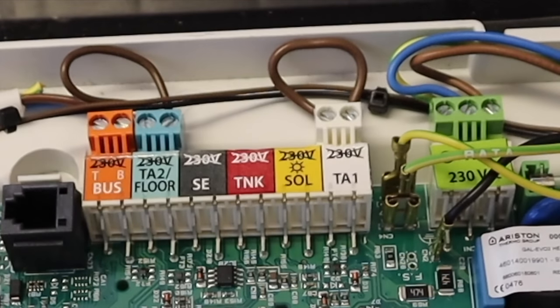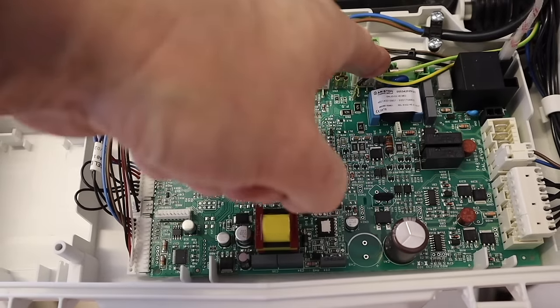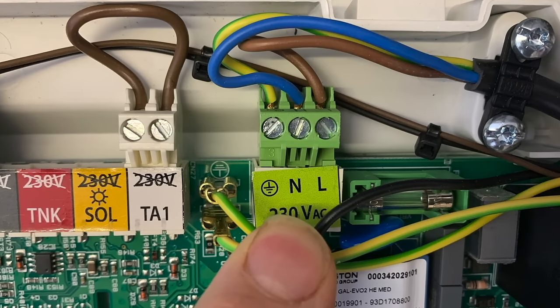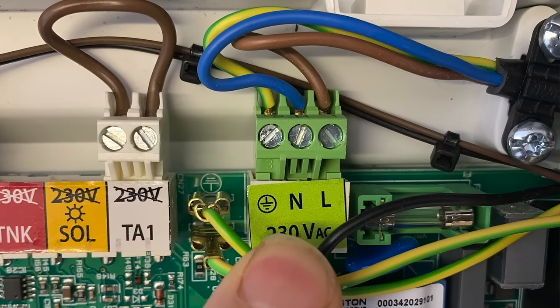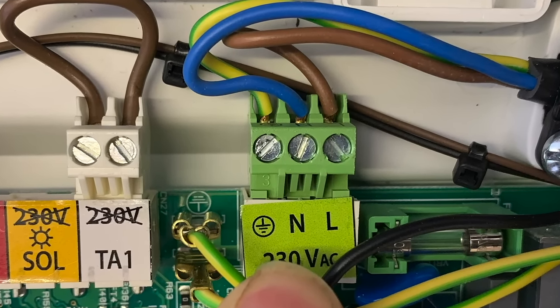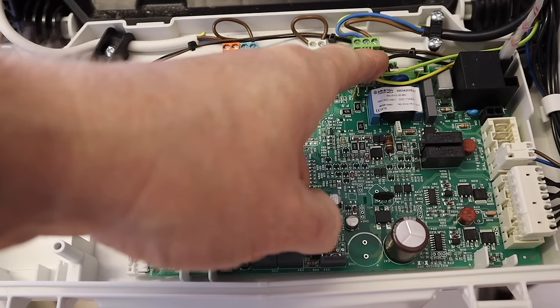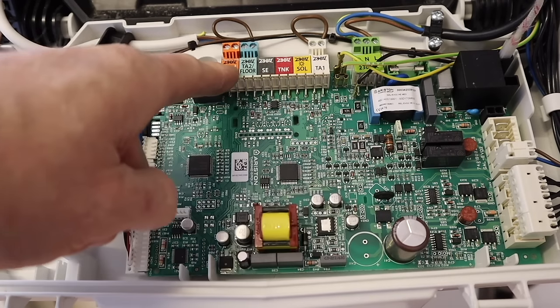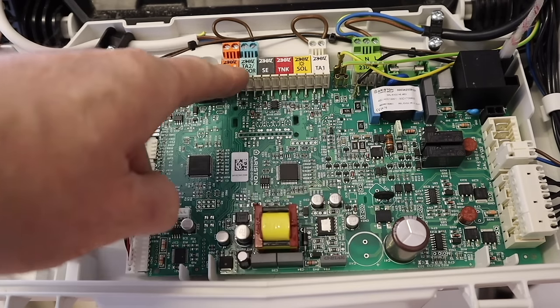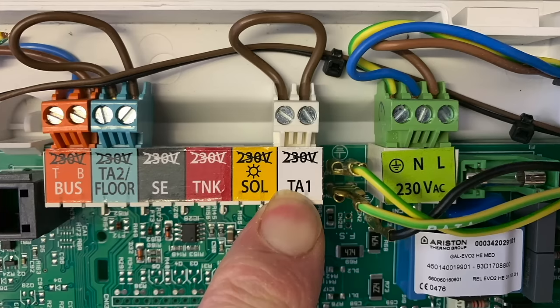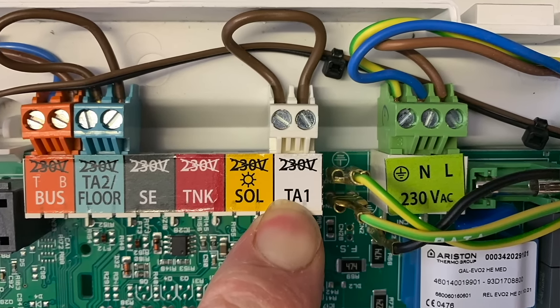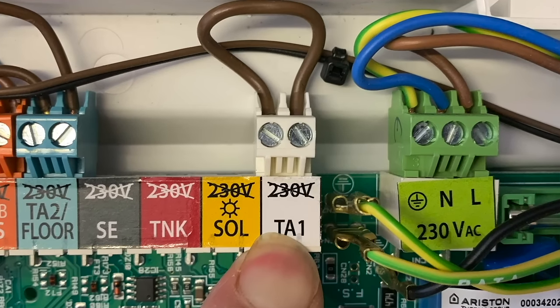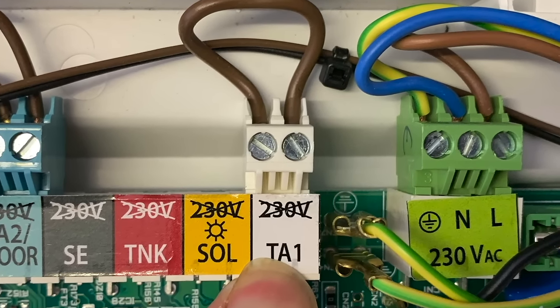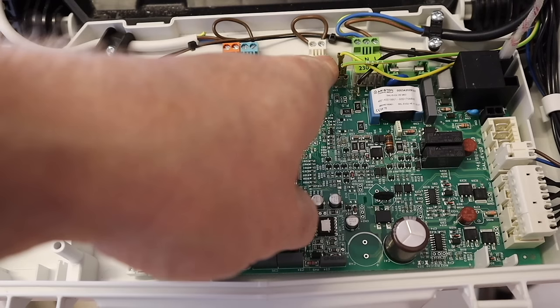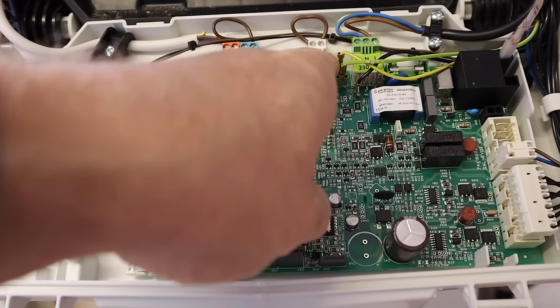This has been tested. This is dead. There is no power going to this printed circuit board. So we can see here, this is where our power comes in. In the UK, we've got 220 to 250 volts AC, alternating current, at 50 hertz. Now, this on the Ariston is all low voltage. You can see this TA1 here. This is where non-Ariston thermostats get connected. So any stat here which isn't an Ariston stat would go into this section here.